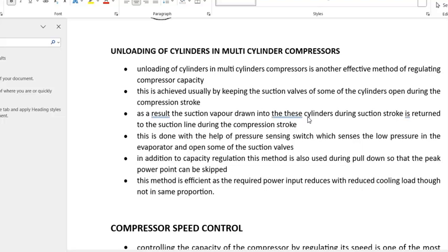This is done with the help of pressure sensing switches, which sense the low pressure in the evaporator and open some of the suction valves. In addition to capacity regulation, this method is also used during pull down so that a peak power point can be skipped. This method is efficient as the required power input reduces with reduced cooling load, but not in the same proportion.